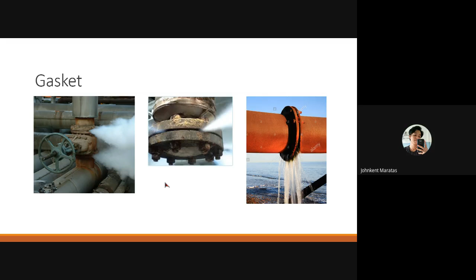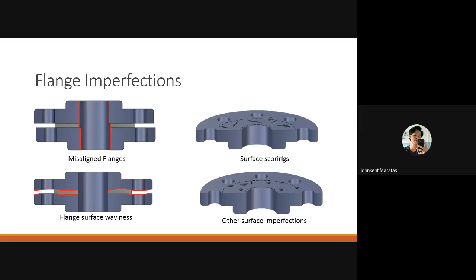And once seated, a gasket must be capable of overcoming minor alignment issues like these: the misaligned flanges, the flange surface waviness, and some surface scorings and other surface imperfections from the flanges. So this is how it looks when the gasket is applied in between the flanges. It is bolted in between.